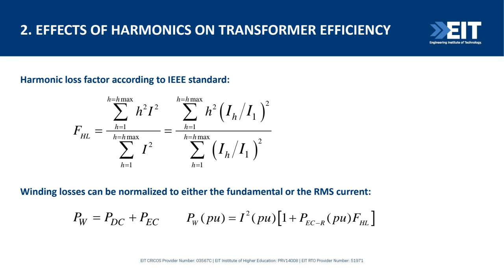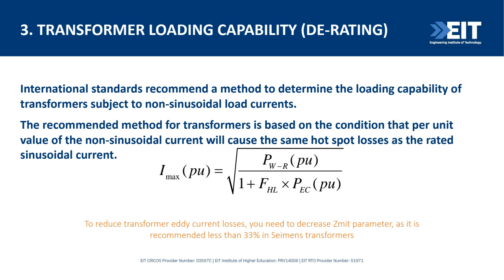Now, if you look at the international standards, they recommend a method to determine the loading capability of transformers subjected to non-sinusoidal load currents, especially IEEE 519, of which I said the latest version came out in 2014. It's based on the condition that a per unit value of non-sinusoidal current will cause the same hotspot losses as the rated sinusoidal current. And it gives us this expression for the maximum current that we can have in the per unit system. To reduce transformer eddy current losses, we need to decrease the Zmit parameter, which is very important in transformers if you look at the standards. So the loading capability of transformers is affected by the harmonics, and it has been standardized. You can find it in different international standards and our Australian standards as well.